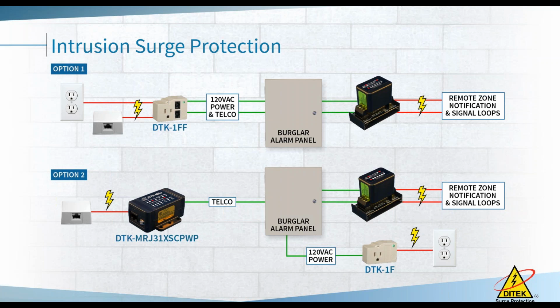That's a device that, I'll tell you, when I go into integrators and end users, I say if you don't put a 1F on everything you plug in, shame on you. They're relatively inexpensive, with surge current ratings in the 40 to 50,000 amp range. They're a tank. They also come with long center screws so you can screw it into your transformer, into the device, to hold everything in place in the wall.